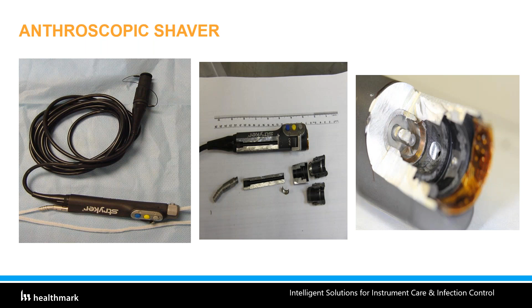So as you see, part of the issue, when I fed back my information to the FDA, was that the design of these shavers really does not allow for adequate cleaning. At the time, the conversation between the FDA and the device manufacturer was that the users were not following the instructions for cleaning. And really, when you look at this, at some point it's impossible to clean some of these. While we were looking at those shavers, we found that really anything with a lumen that you cannot see with the naked eye could have those issues.